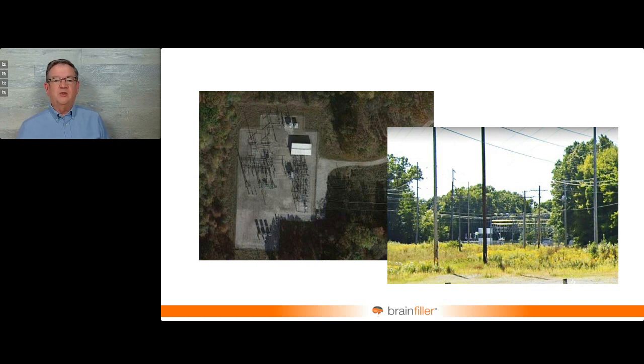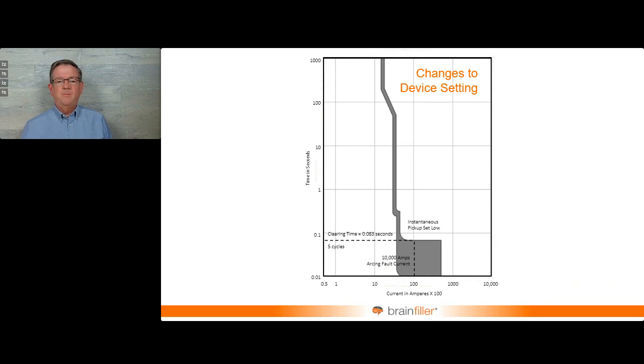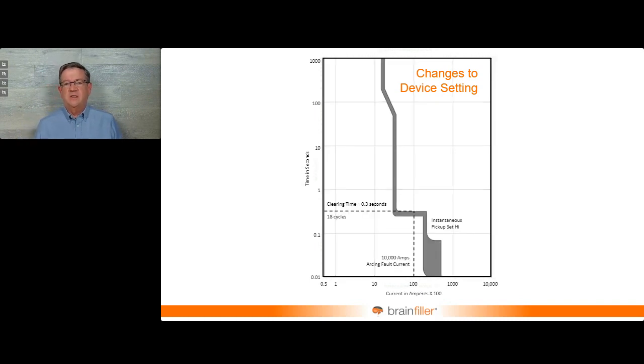So if you see construction activity from a utility in a given area, it's a good idea to investigate, hey, are you adding a substation? How's that going to impact things? And even device setting changes. You may have a device that has settings like this for a given amount of short circuit current, and then somebody changes the settings. That has a big impact on the clearing time. Why on earth would somebody change the settings?